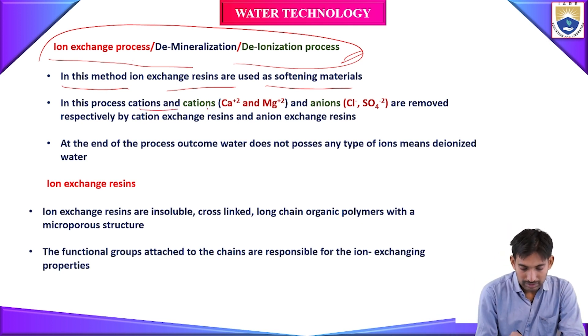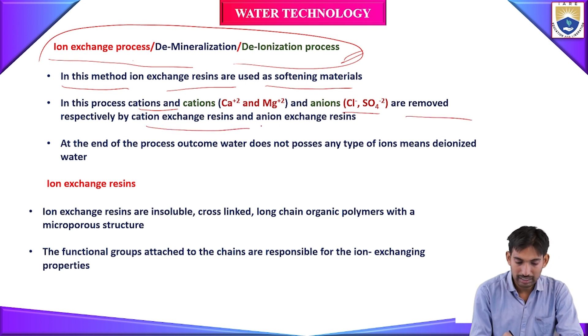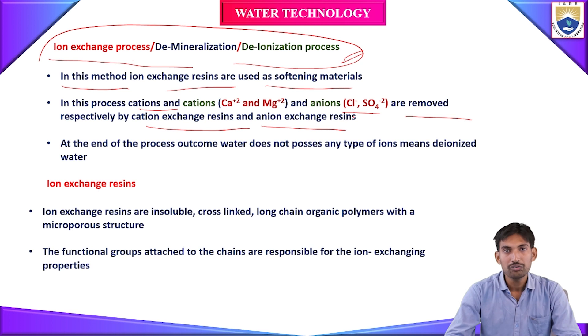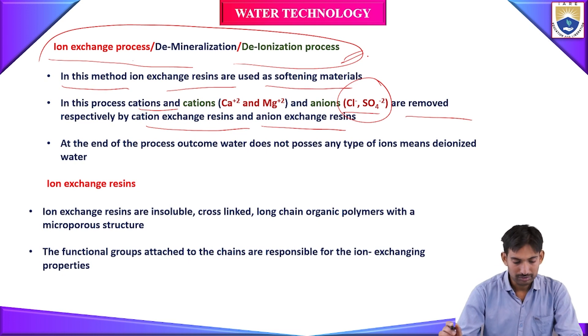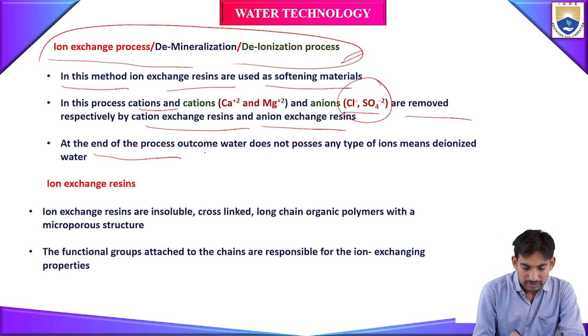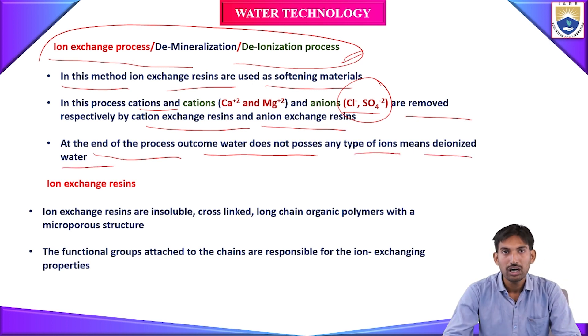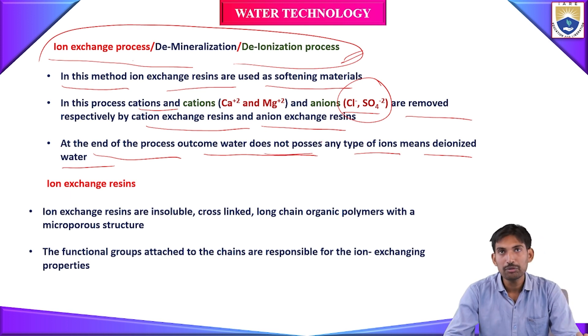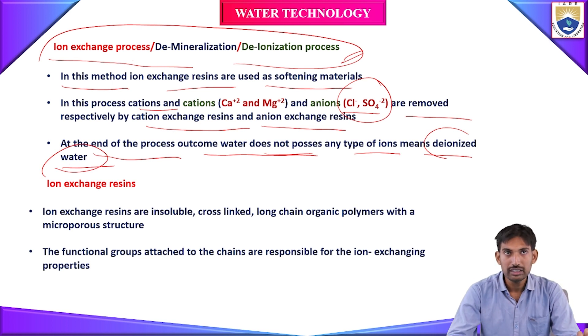In this process, cations — nothing but calcium and magnesium — and anions — nothing but chloride and sulfate ions — are removed by cation exchange resins and anion exchange resins respectively. By using cation exchange resins we separate the cations, and by using anion exchange resins we separate the anions. At the end of the process, the outcome water does not possess any type of ions — we get deionized water.